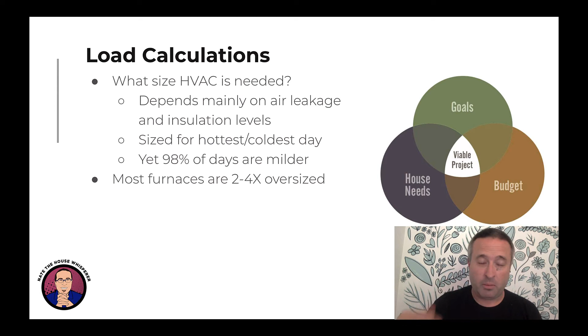So test-in, the house as it stands, is right about a 3-ton house, 36,000 BTUs. Target 1 at 2,200, and we moved some R values a little bit, but basically when you get to about an R20 in the attic, going above that is a diminishing returns curve. So it depends on a bunch of factors, where you live, install quality, a bunch of things. But by reducing the blower door by about a third and going from like an R19 to an R38 in the attic, we step down a half a ton. If we get the house tighter still, and this is basically the same R values between these two, we lose another 4,000 BTUs. So this house in Cleveland, Ohio is basically a 2-ton house when it's 5 degrees out.